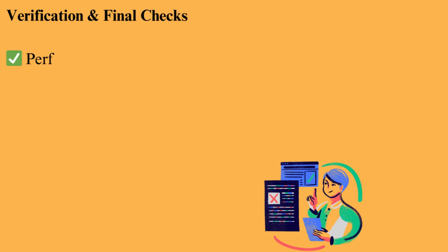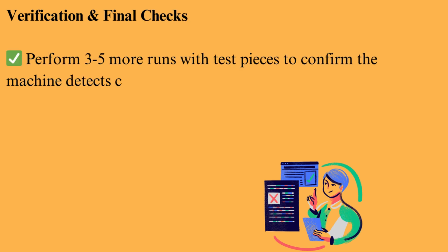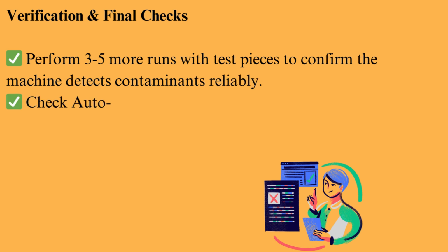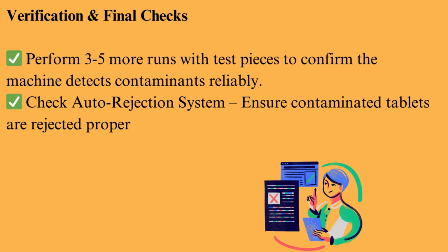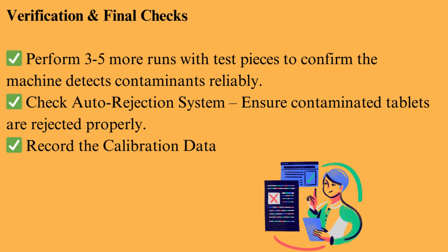Verification. Final checks. Perform 3 to 5 more runs with test pieces to confirm the machine detects contaminants reliably. Check the auto rejection system and ensure contaminated tablets are rejected properly. Record the calibration data and maintain logs for audit and compliance purposes.